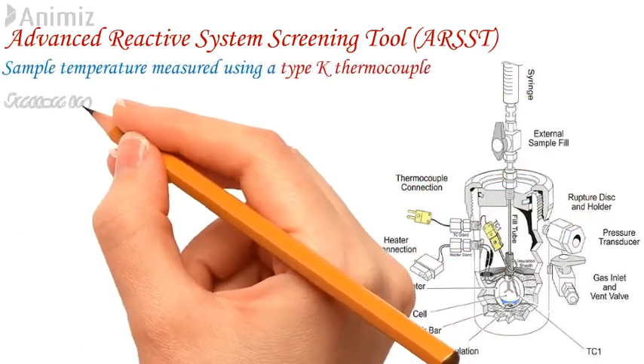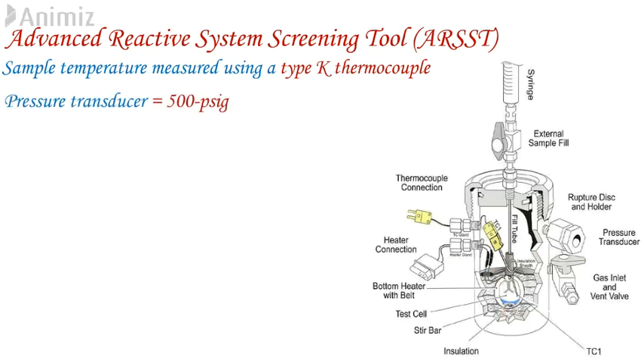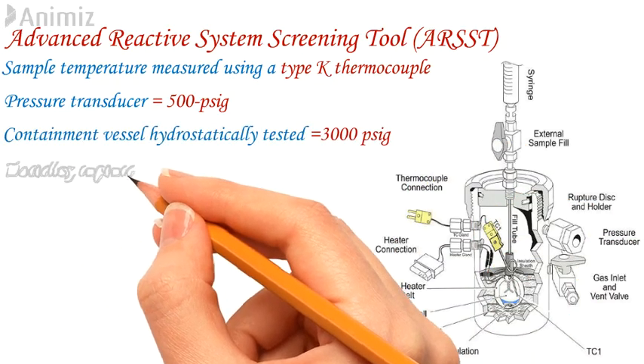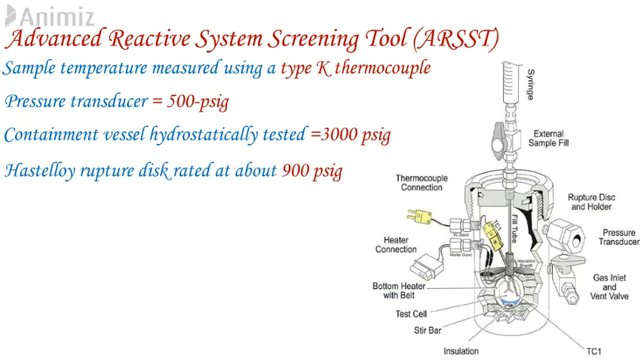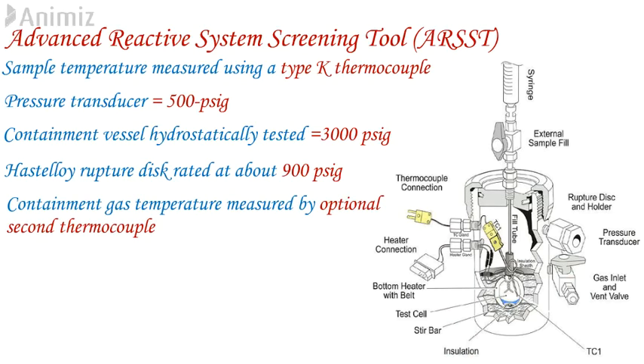This key feature allows the measured data to be directly applied to process scale. Sample temperature is measured using a type-K thermocouple, and a 500 PSIG pressure transducer is standard. The containment vessel is hydrostatically tested to 3000 PSIG and has a rupture disc rated at about 900 PSIG. The containment gas temperature can be measured during a test using an optional second thermocouple. The control box contains a temperature and pressure amplifier and a heater power supply. A single heater circuit powers the 24-ohm bottom heater, delivering up to 17 watts.